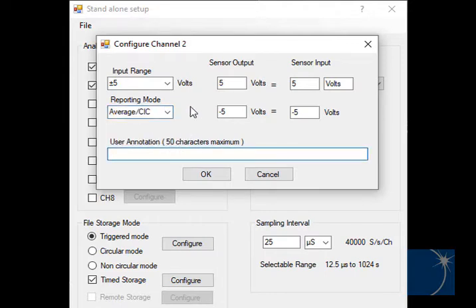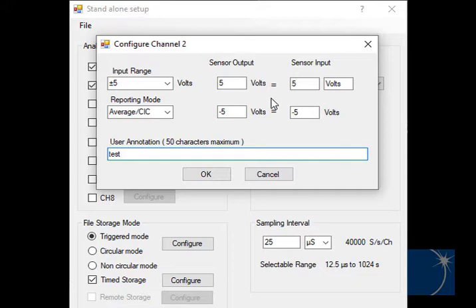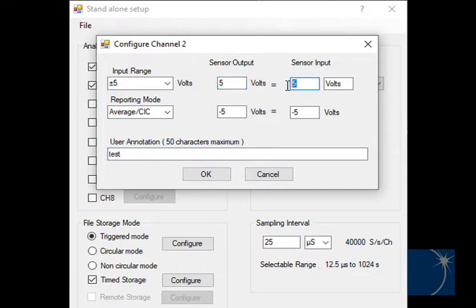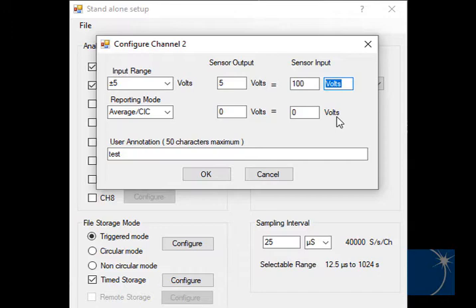You can annotate or label a channel and scale a channel to display meaningful engineering units. In this case, we have a pressure transducer with a 0 to 5 volt output and a 0 to 100 psi measurement range. So we'll enter 5 for the upper level sensor output, 100 for the upper level sensor input, and 0 and 0 for lower level sensor output and sensor input, and then change the engineering units to psi.